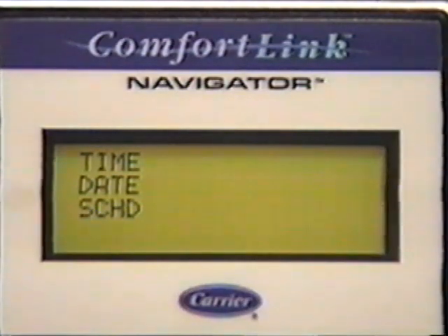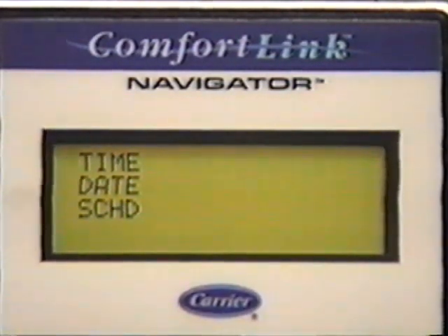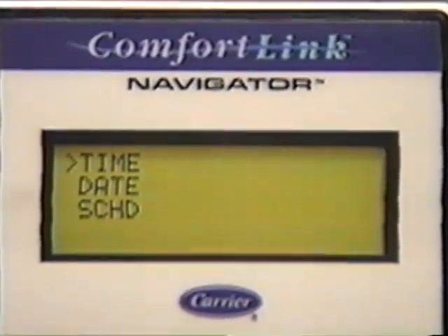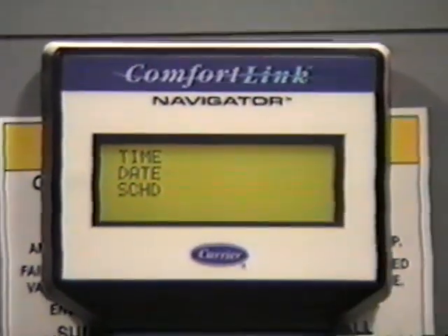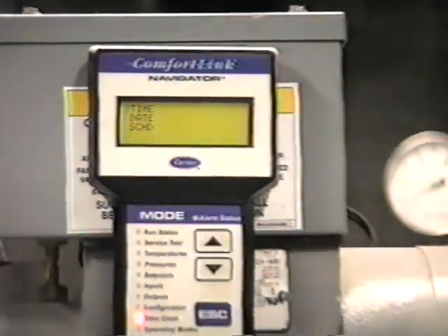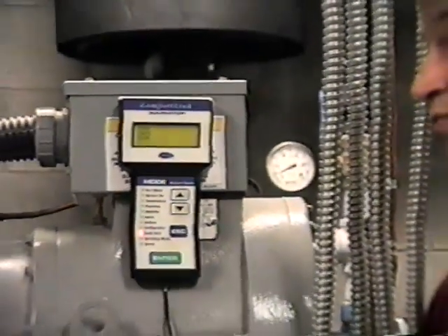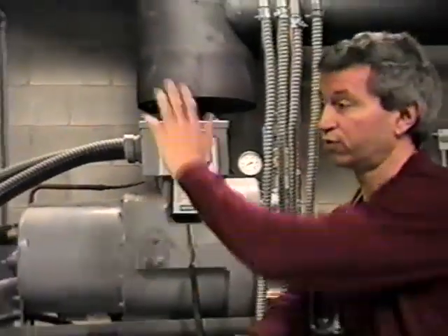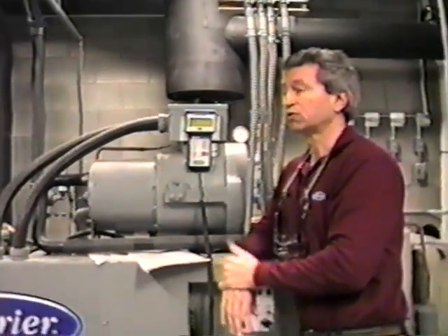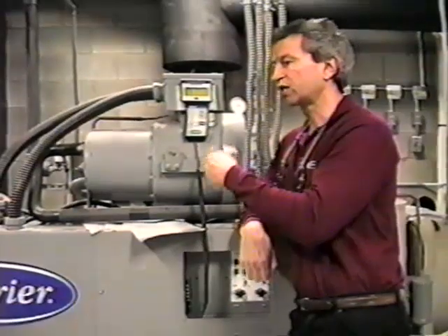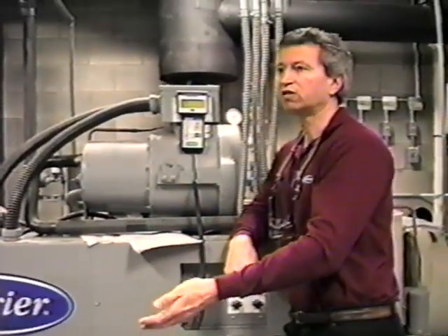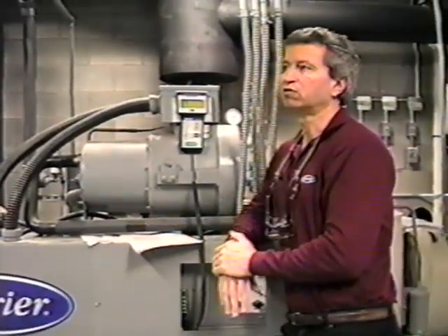Time clock, basically is where you set your time and date, and then there's a schedule there. You're not using any schedule. There's a choice where you can tell the processor to either look at a time schedule that's programmed in this machine, or just ignore it. And we've programmed it to ignore it because we don't want to conflict with your smart drive. So there's no time schedule. When this switch is on, it's essentially going to run 24 hours a day, 7 days a week, as long as you want it to.